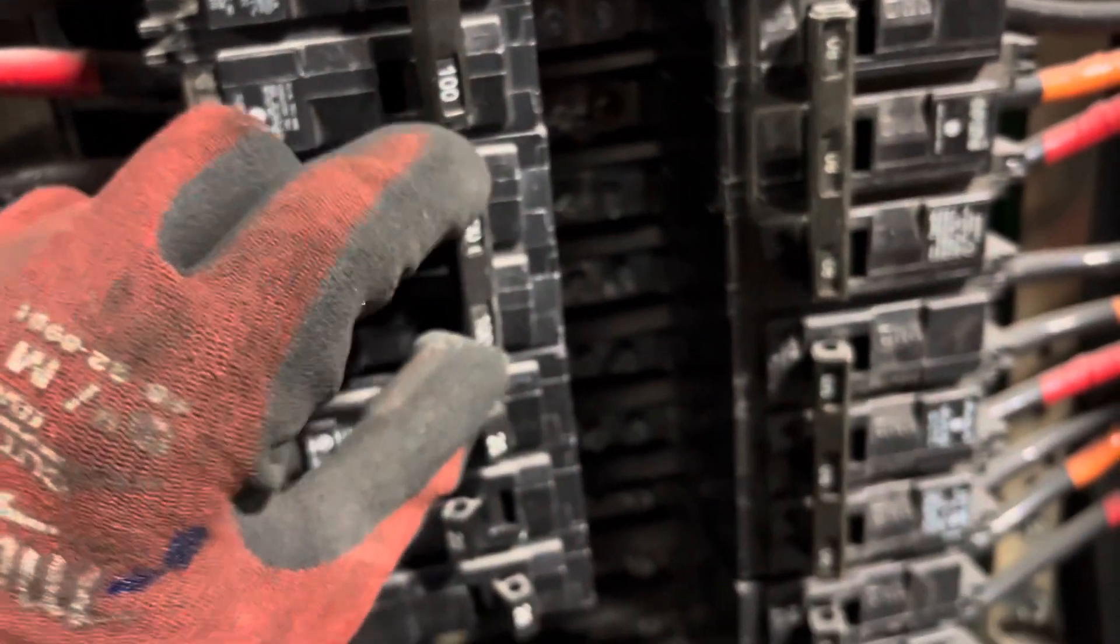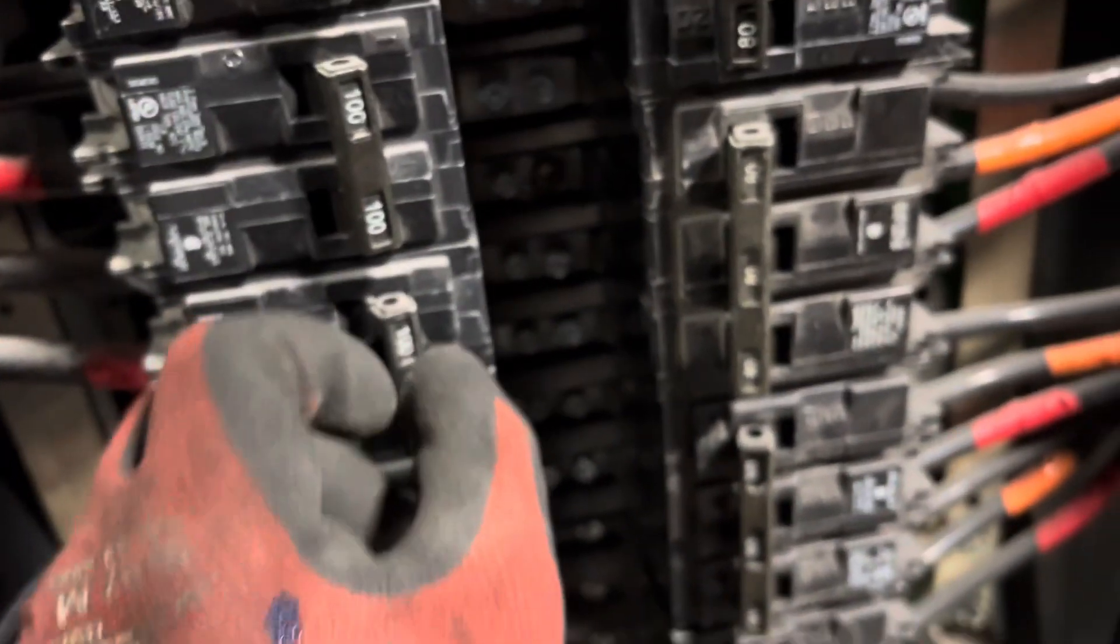On this one, what was the other one? Oh yeah, he had a problem with the Tesla wiring. There's a Tesla charger he put in, and it was blowing circuit breakers and wasn't working. When I went over there, what he did was he took one wire out here—supposed to be on 240. So it has like these two right here. You see the little bar right there? If one pops, it's supposed to pop two so you don't single-leg and only get half the voltage, because on some things you could damage them. What he did was he put one wire here and one wire way up on another one so he could find his 240 volts, and it was single-legging and causing problems with the Tesla charger.